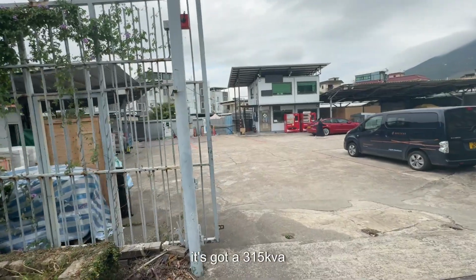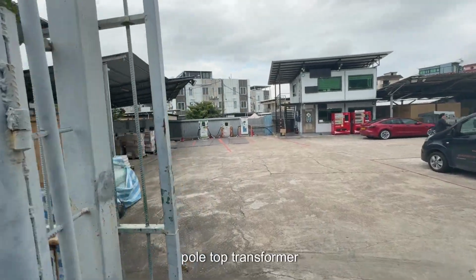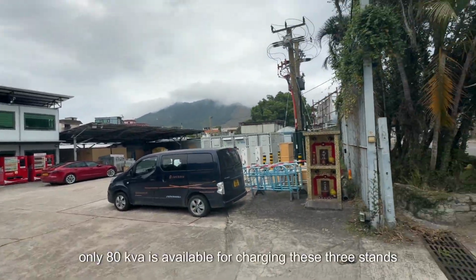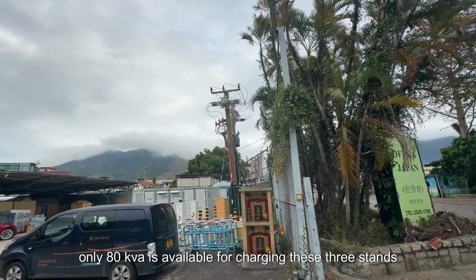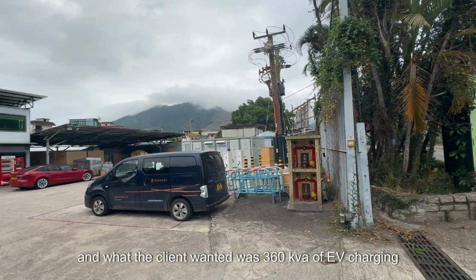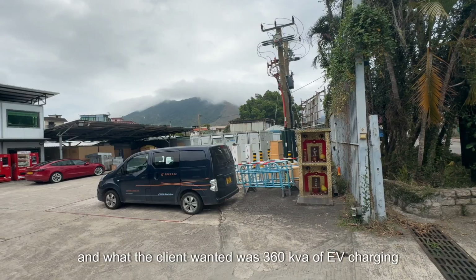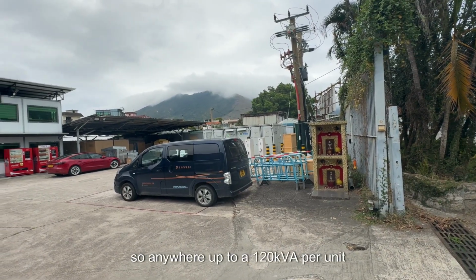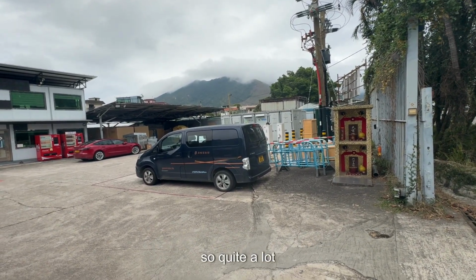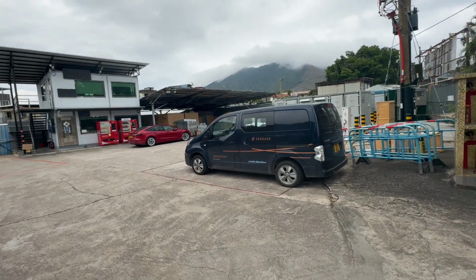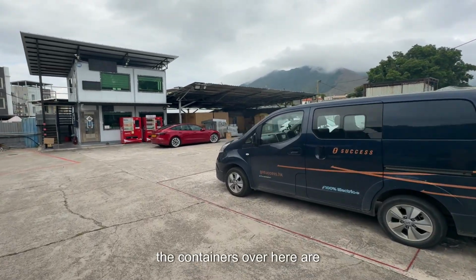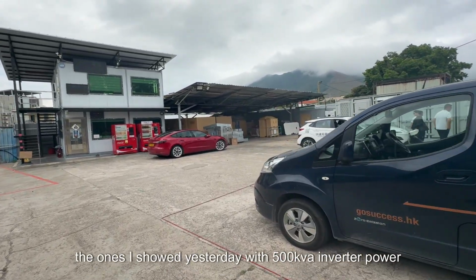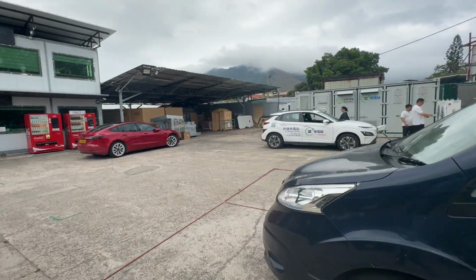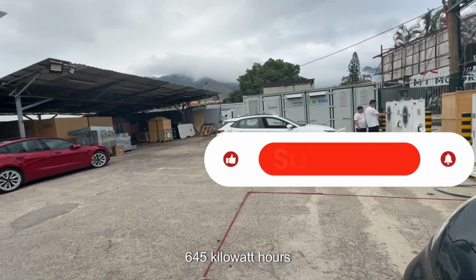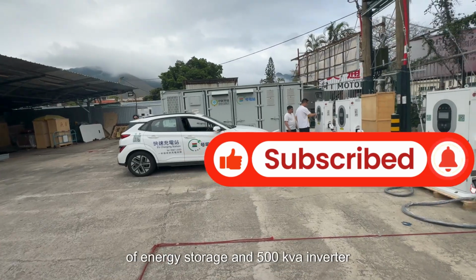It's got a 315 kVA pole top transformer, and of that, only 80 kVA is available for charging these three stands. And what the client wanted was 360 kVA of EV charging, so anywhere up to 120 per unit, so quite a lot. The containers over here are the ones I showed yesterday with 500 kVA of inverter power, 645 kilowatt hours of energy storage and a 500 kVA inverter.